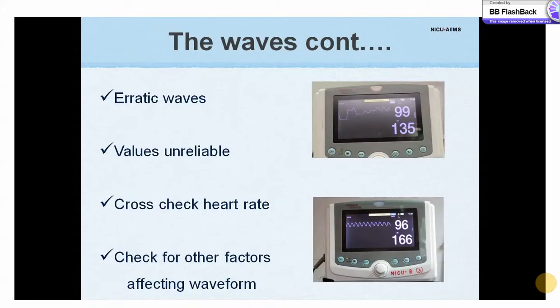If the waves are not uniform, the values displayed are likely to be erroneous. A practical approach is to cross-check the heart rate of the baby with the displayed value — they should match within 10% of each other. The causes of non-uniform waves could be many and should be corrected before attributing any significance to the displayed values.